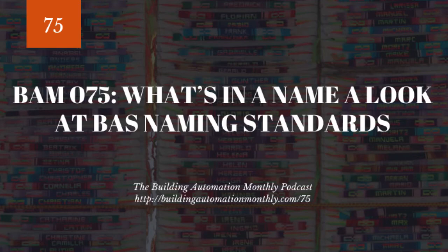What temp is it? And so therein lies the rub. You'd be shocked by some of the naming standards I've seen, well, lack thereof, where folks just literally call things whatever they want. Like you've got space things called space temperature, and they're misspelled, and it's just all sorts of ugly. Because what that ends up doing is now, if you want to search, if you want to do reporting, if you want to do any aliased graphics, all sorts of things that are common in the building automation system person's day-to-day role, you can't do any of that.